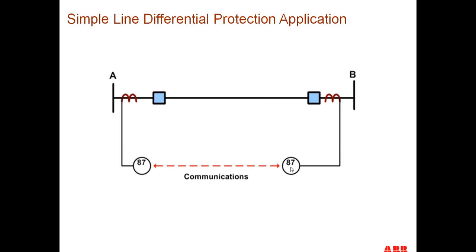and the information is exchanged over a communications line between the two 87 relays that share the information, and then each terminal makes a decision about whether to trip or not, depending on whether the fault is internal or external. It's all based on the simple Kirchhoff's law that the current entering a node has to be equal to the current leaving the node.